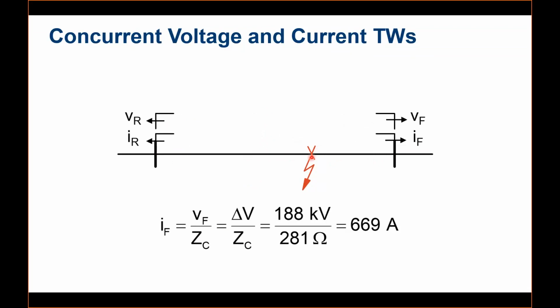Once it travels from the point of fault, it reaches the station on your left and the station on your right. One more important thing is that it's not only the voltage change. Whenever there is a disturbance, there will be an associated traveling wave in the current as well. We call this the current traveling wave. There is a simple relationship between voltage and current: we can find the traveling wave, or the disturbance, in the current with Ohm's law, that's voltage divided by the impedance.